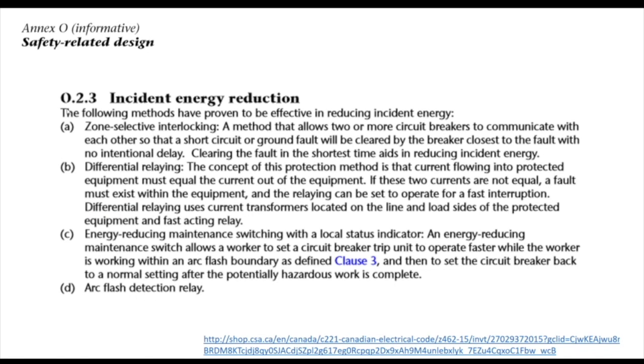Zone selective interlocking: a method that allows two or more circuit breakers to communicate with each other so that a short circuit or ground fault will be cleared by the breaker closest to the fault with no intentional delay. As we know, the longer it takes, the more incident energy, heat, can be applied to the fault area where the worker could be. Differential relaying, super fast relays on either side of a transformer typically. Fast is good, slow is not good when you're talking about arc flash calculation.